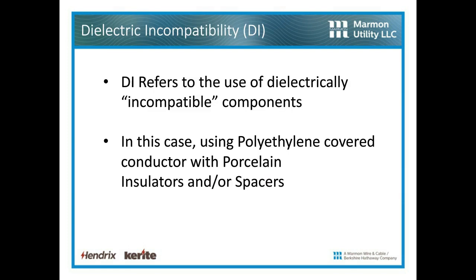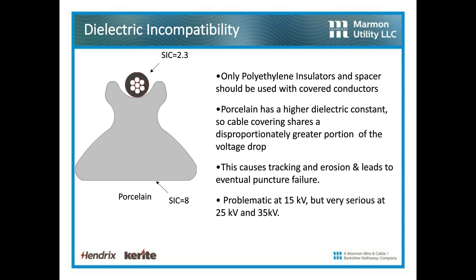It has to do with dielectric incompatibility. Dielectric incompatibility refers to the use of dielectrically incompatible components, in this case using polyethylene covered conductor with porcelain insulators or with porcelain spacers. I don't know if anybody sitting in today is old enough to have ever seen a porcelain spacer, but in the Stone Age we had them, and yes, most of them have been removed. But you can see dielectric incompatibility. We've got a covered conductor with a dielectric constant of 2.3 sitting on a porcelain insulator with a dielectric constant of between 8 and 9. Only poly insulators and spacers should be used with covered conductor.